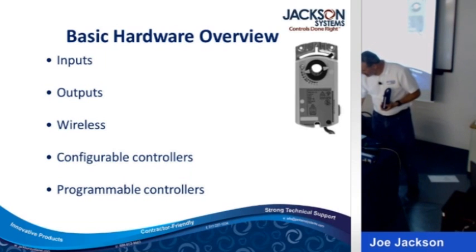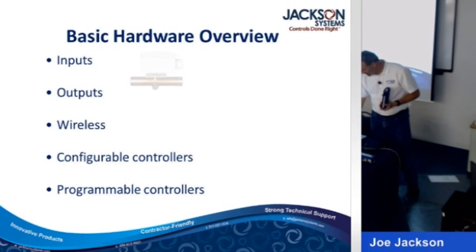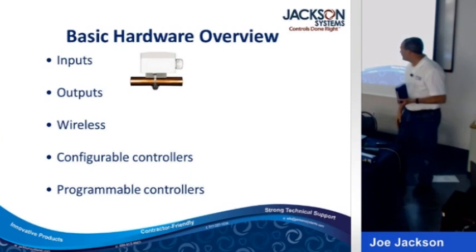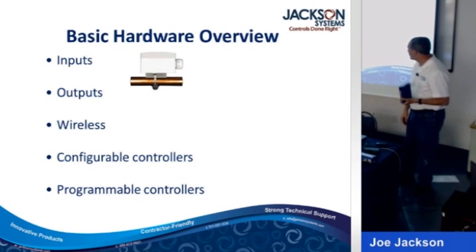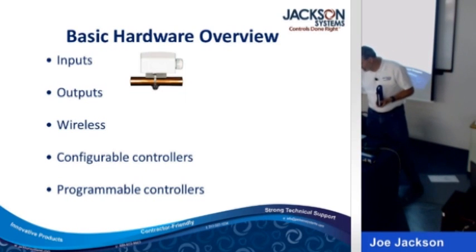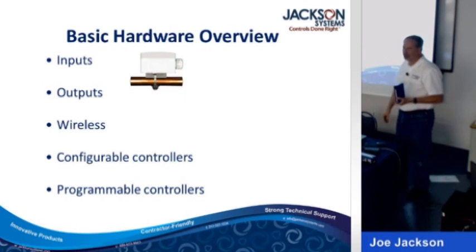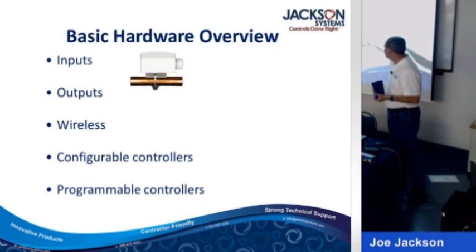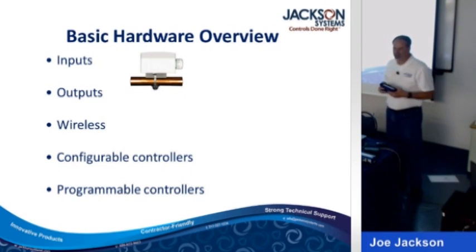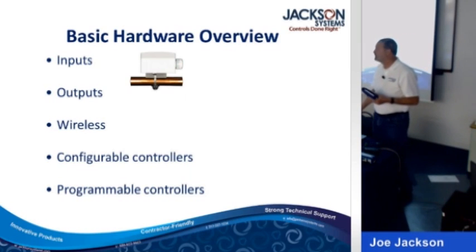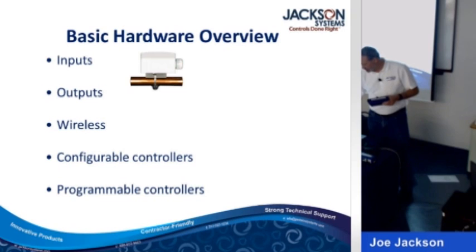Brought up a picture of a damper actuator. Don't know why. I think the slide's a little out of whack. That's actually a picture of a strap-on wireless pipe temperature sensor. Great idea if you want to put a pipe temperature sensor up in the ceiling. And most of these temperature sensors actually get their power from light. So when you put it up in the ceiling and close the ceiling up and the light goes away, your sensor stops reading.